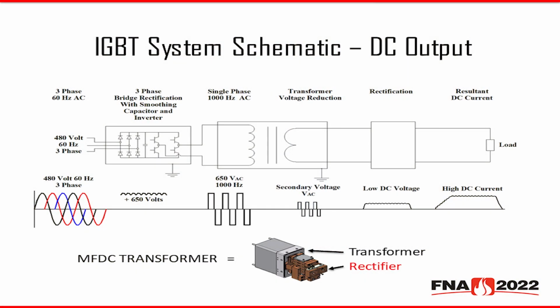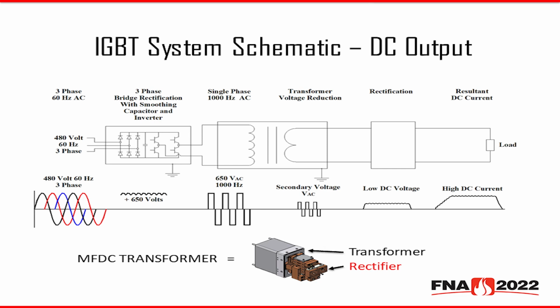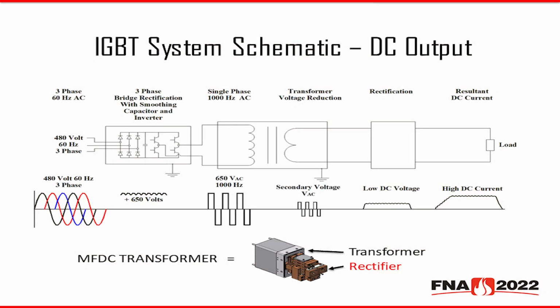Other question? If you go back to that last slide, if you tell us what sort of power those transformers up on top of the furnace are, if I make an example. Oh, yeah. So for that application, I have to do some quick math here. So for this application, there's 5 zones. The 3 inner zones are 248 kVA, and then the outside zones are 86 kVA.